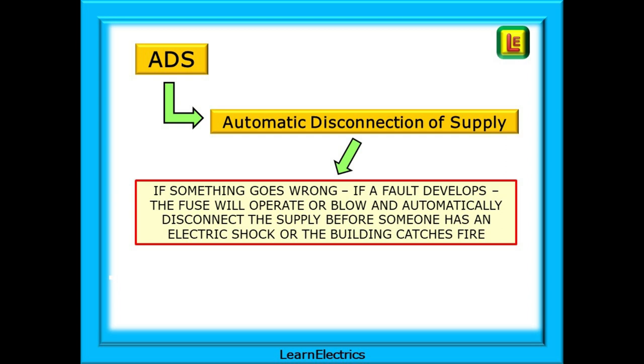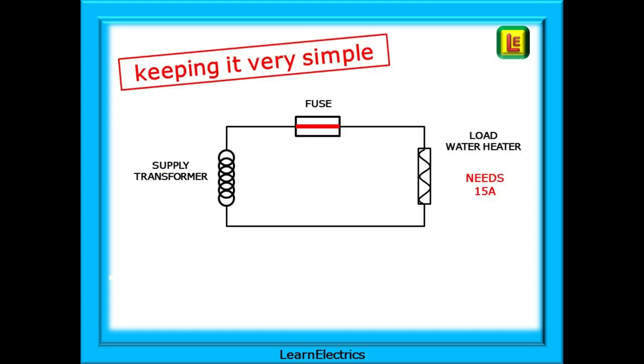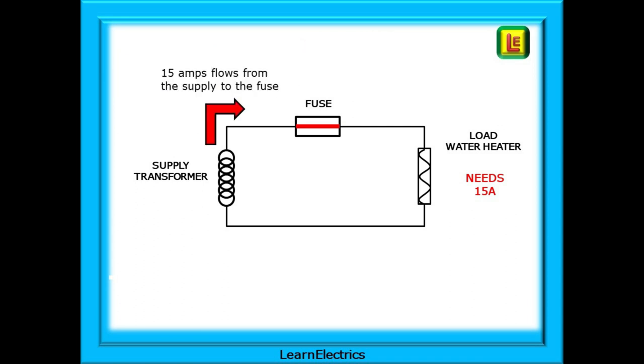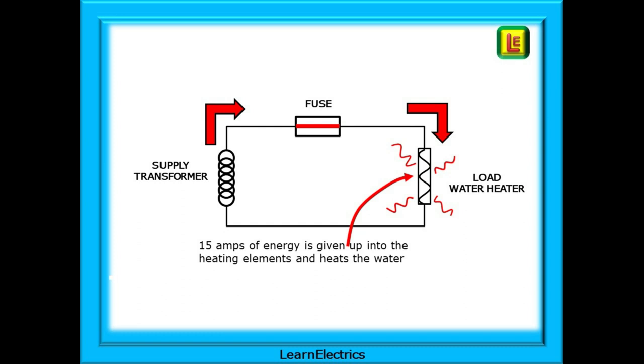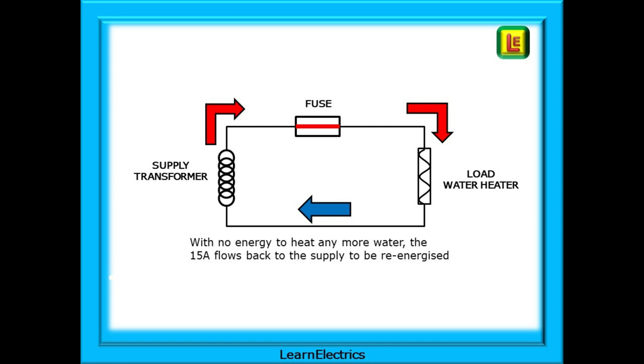A fault occurs, the fuse blows automatically and disconnects the supply to that circuit. Keeping it very simple and just concentrating on a two-wire circuit, we have a circuit that supplies a water heater. The water heater draws close to 15 amps when in use and is protected by a 15 amp fuse. 15 amps flows from the supply transformer, either in the building or down the road somewhere, through the fuse to the water heater. At the water heater the energy in the electricity is given up into the heating elements, heating the water. The current then leaves the water heater having given up all its energy, and flows back to the supply transformer where it can be re-energized and repeat the whole process again.